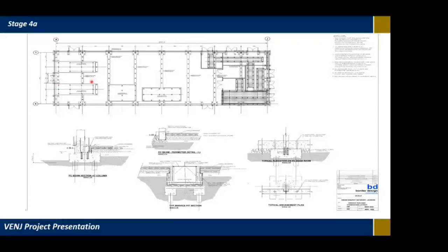Each heat pump is around 12 to 13 tons, so it's quite a heavy piece of kit. We needed a dedicated slab to mount it, and that slab runs to the edge of the building, forming an external plinth. So for the current install and future install, the heat pump can be craned on as one package and slid into the energy centre. All that coordination had to be done up front to make sure it was buildable with a contractor. You can also see the slabs for the thermal stores, boilers, and pressurization, all built in.